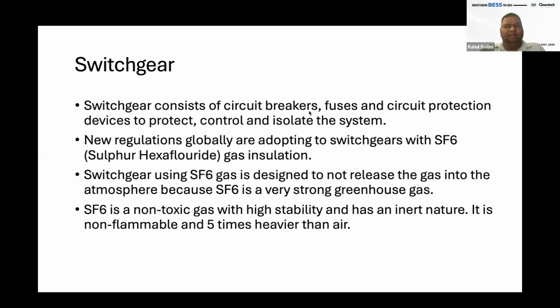If there is some issue and you want to isolate that particular part of the project, switchgear comes into play. A new regulation in certain countries is asking for SF6 based gas insulating switchgear. SF6 is a very inert, non-reactive, and dense gas, but a highly potent greenhouse gas. Still, it's accepted for insulation, it's non-toxic, and systems are designed so the gas cannot escape.